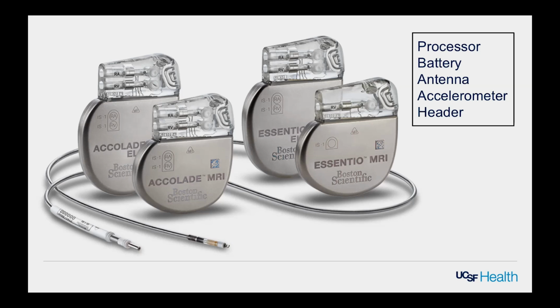These pacemaker generators have a lot of circuitry in them. There's a processor in there. There's a battery in there. This clear top part called the header, there is an antenna. This antenna is what allows us to communicate with the pacemaker generator through the skin. So once the device is implanted, it's completely under the skin, and we're able to talk to the device using what we call an interrogator. So that allows us to see what the device is seeing. It allows us to make programming changes to the device. It allows us to make measurements of the lead to make sure the device is functioning appropriately.